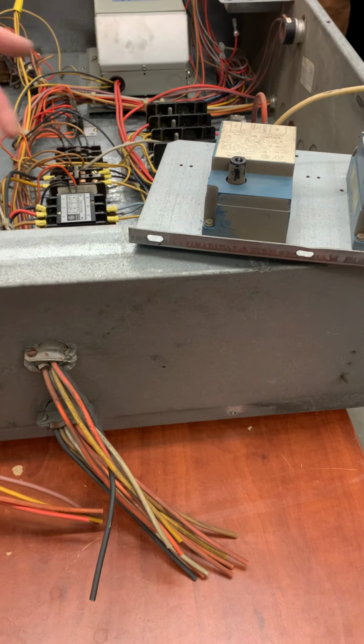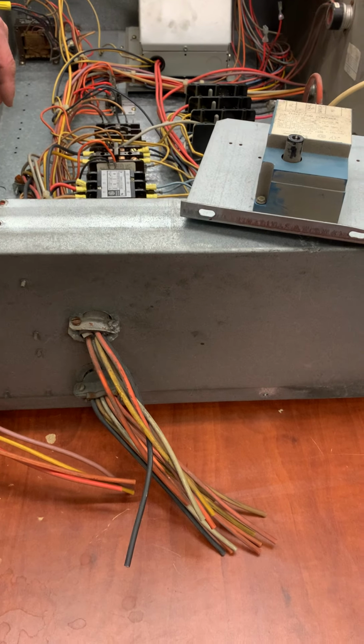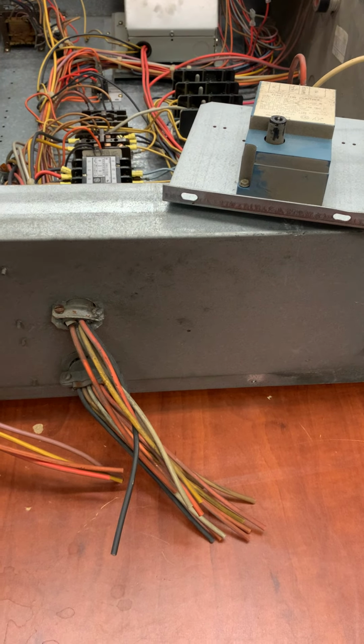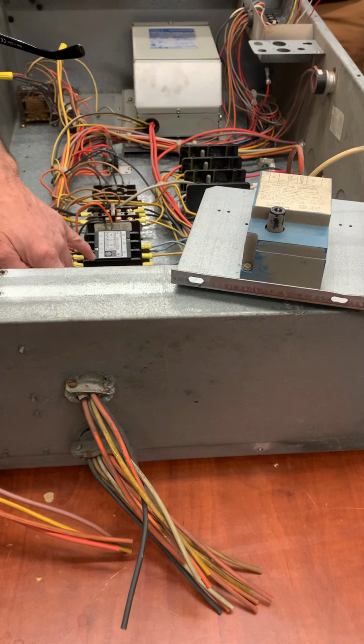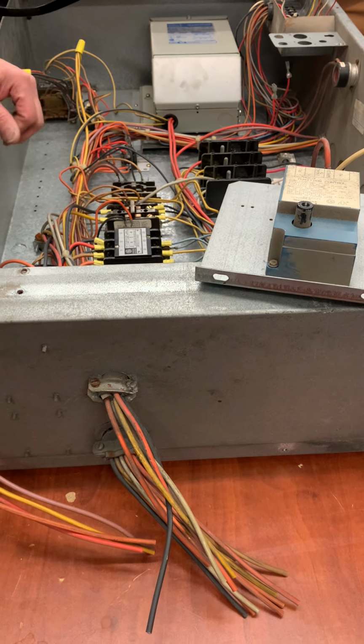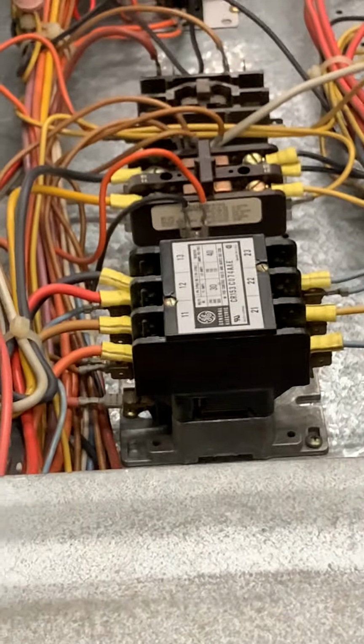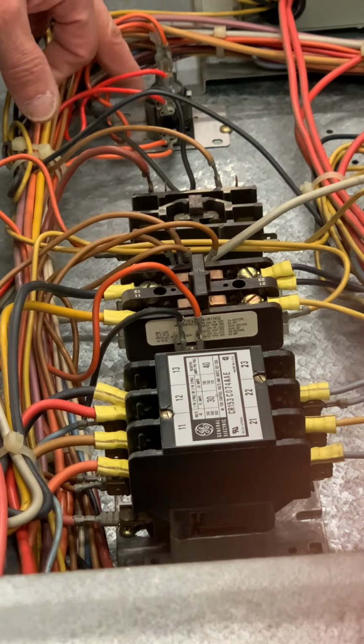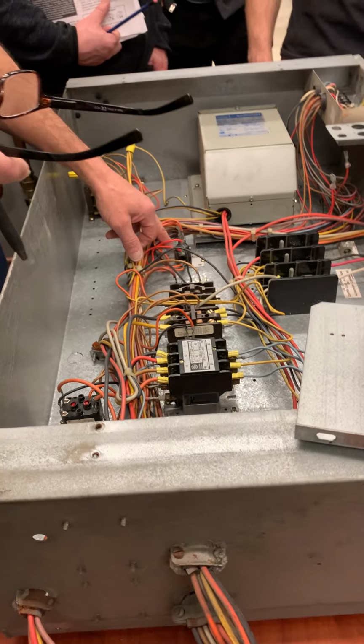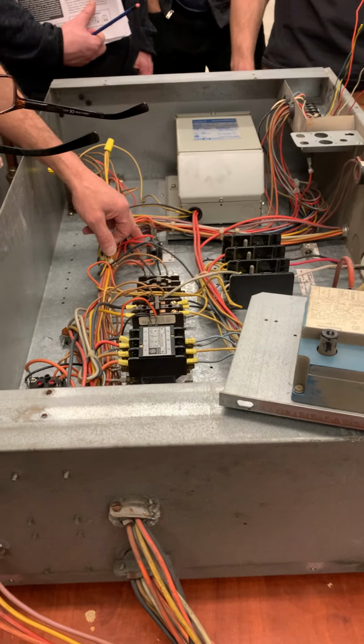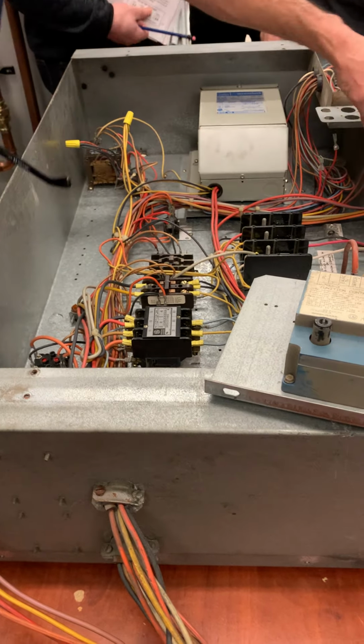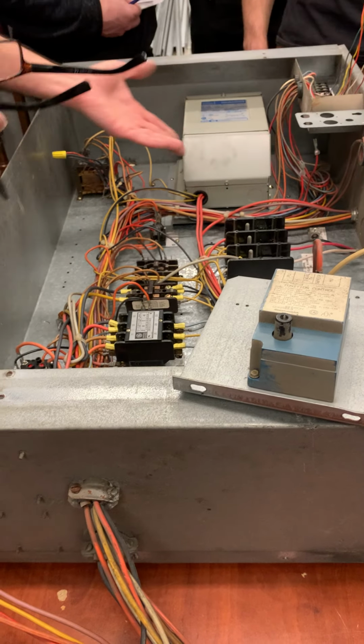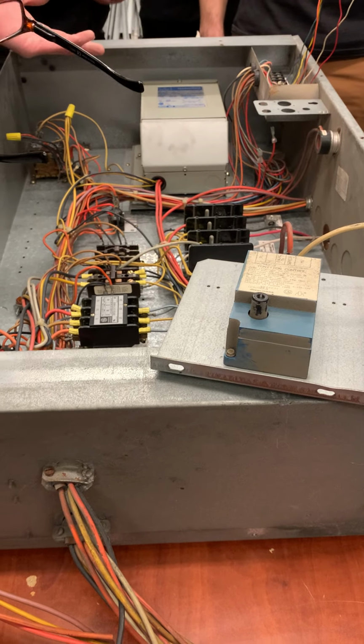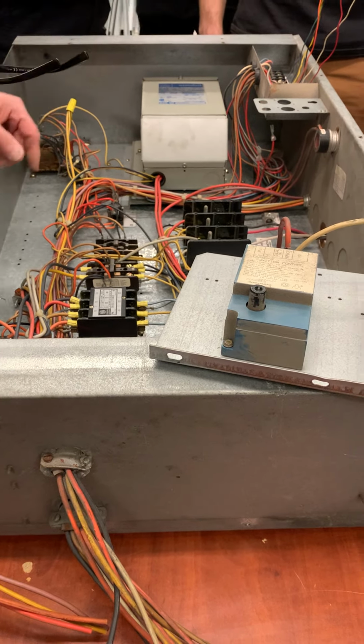I'll look at a unit, I'll say, hey, 2-stage, 5-ton unit or 10-ton unit. I know these two are for the compressors, the smaller one's the indoor motor. I'll look at these, I know what they're doing. They're going to be running the fan operation in the heat mode. I'll look at this item, it's sensing the temperature right here, the sheet metal. The only reason I want to sense the sheet metal temperature is so I can have a low ambient thermostat shut off the compressors if it's too cold.